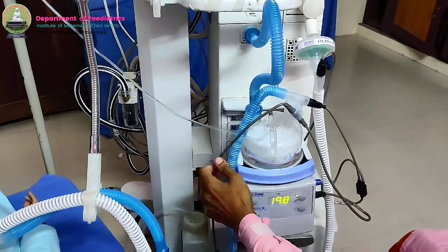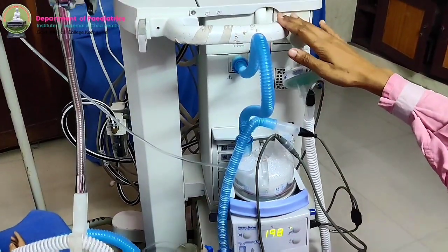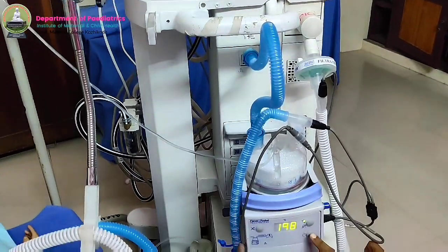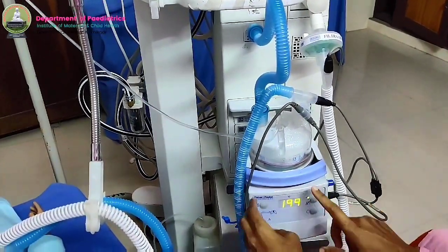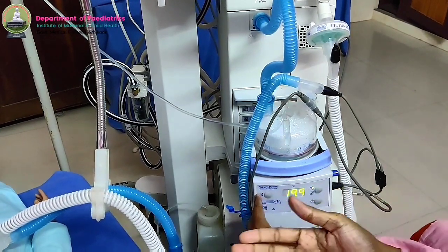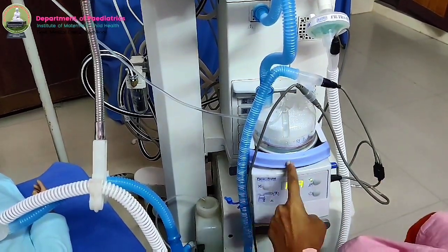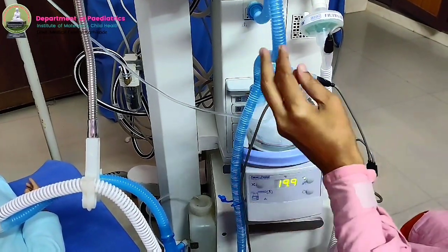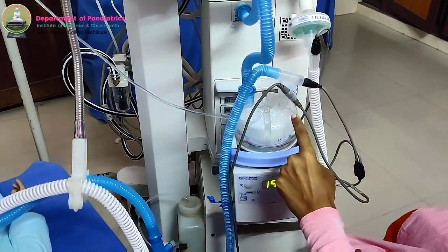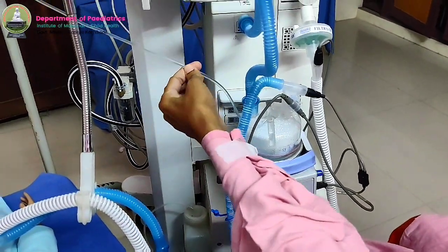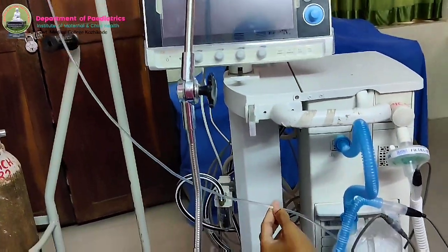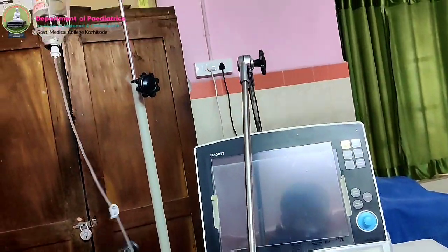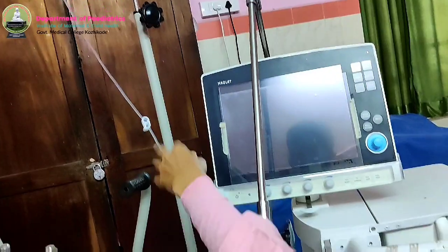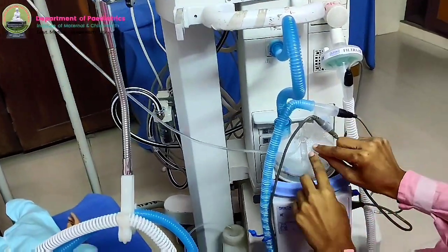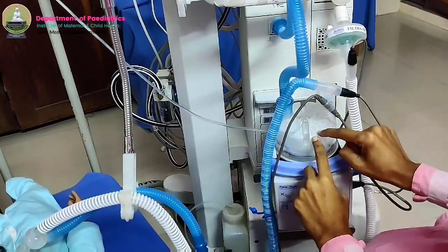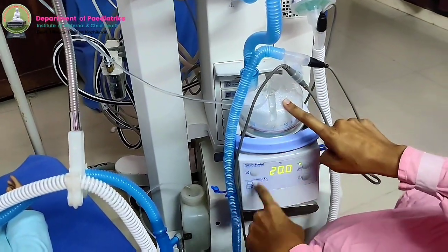Then when you are keeping the ventilator in the standby mode, always make sure that you switch off the humidifier. Otherwise it will get heated up without the patient being ventilated and the humidifier may get damaged. So near the humidifier, many points of air leak are there. One of the air leak point is this port for entry of sterile water. If the lock is not properly closed, air can escape through that also. In some humidifier, there will be a cap for filling the humidifier with a syringe. That also has to be properly closed.